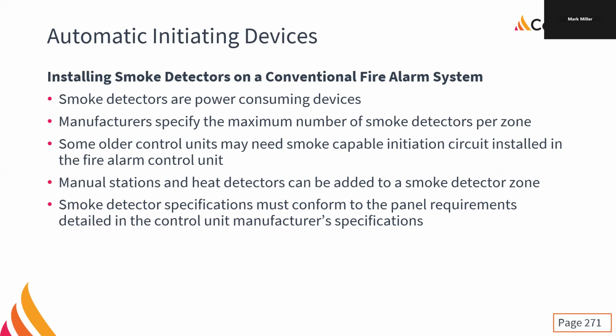But we also have to be careful that the actual smoke detector conforms to the panel requirements. It has to be officially listed as being compatible with the control unit. Every control unit out there has installation manual documents, and you can usually find them just by shaking the Google a little bit. There is a list of approved detectors, and if the detector is not on that list, you cannot install it. It might work just fine, but it might not work just fine in every situation.